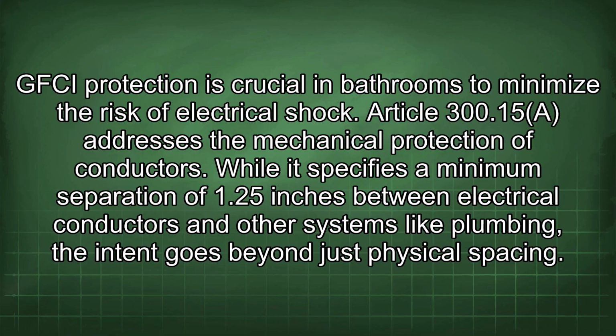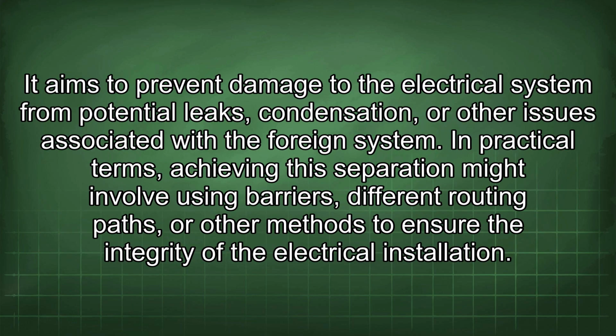Article 300.15 addresses the mechanical protection of conductors. While it specifies a minimum separation of 1.25 inches between electrical conductors and other systems like plumbing, the intent goes beyond just physical spacing. It aims to prevent damage to the electrical system from potential leaks, condensation, or other issues associated with the foreign system. In practical terms, achieving this separation might involve using barriers, different routing paths, or other methods to ensure the integrity of the electrical installation.